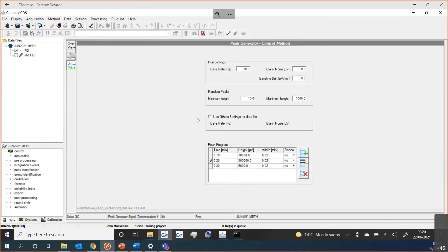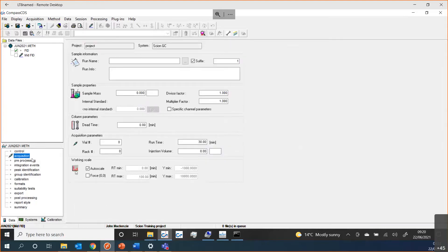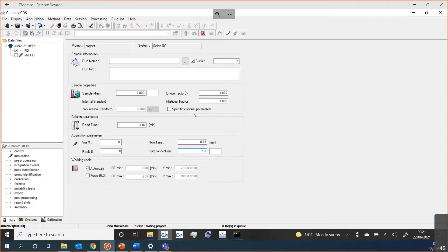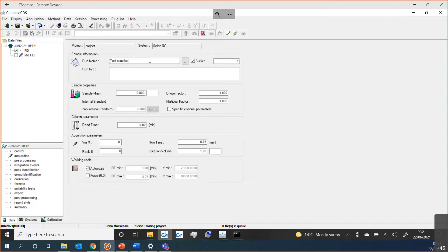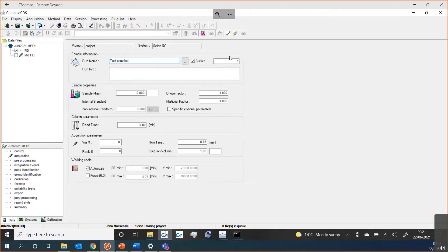As you can see, you can quite quickly build up a method. We want just a 0.75 minute run. We can set what the injection volume is going to be. We can also set what the run name is going to be for every run that we use this method with. We could just give it a simple name, test samples or something like that. And every time we run the method, our file name would be test samples, and then on the end it would add the number one. Every time we run it, it would increment that suffix, two, three, four, and so onward until you get to 1000 and then it will roll over.